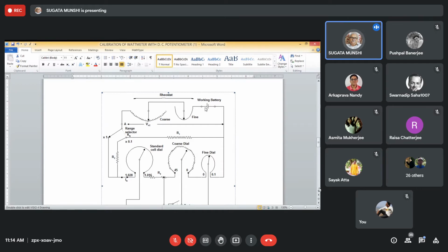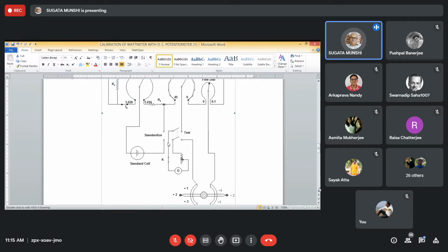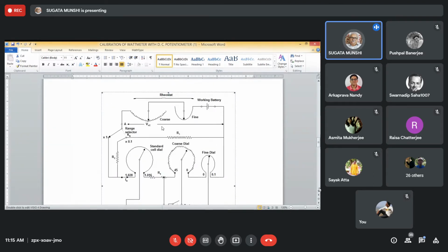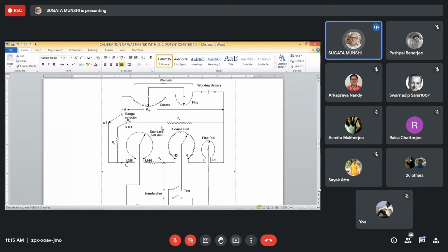You vary the current driven from the working supply through these coils by adjusting the position of this wiper part, and this null detector is in series. When this null detector indicates null position, zero deflection, you can understand that the voltage between this point and that point is 1.0186 volt - that means you have been able to impress a voltage of 1.0186 volts to balance the standard cell voltage. That means you are certain you have been able to inject that working current of 10 milliampere through this combination. Now your standardization is over.